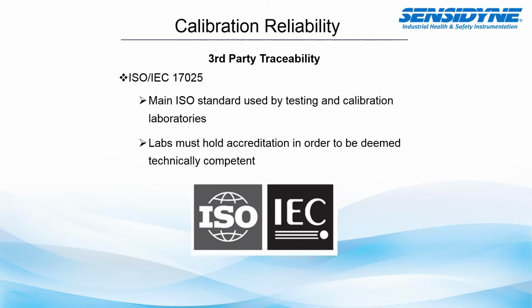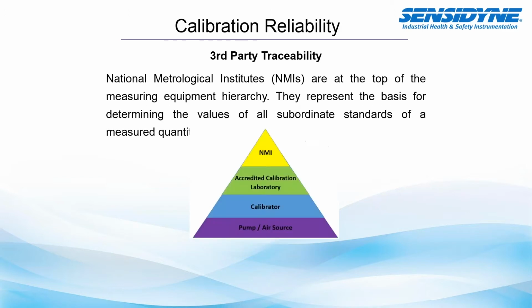So third-party traceability can also include organizations like ISO and IEC. 17025 is a specific ISO standard used by testing and calibration laboratories, and labs must hold accreditation in order to be deemed technically competent. As I mentioned, there is a National Metrological Institute at the top of the measuring equipment hierarchy. They represent the basis for determining the values of all the subordinate standards of measurement. So in this case, you have your pump that you're trying to calibrate, or other air source. And then you use a calibrator to calibrate it. That calibrator should be certified by an accredited calibration laboratory, and that accredited calibration laboratory should have certification or traceability back up to the NMI.